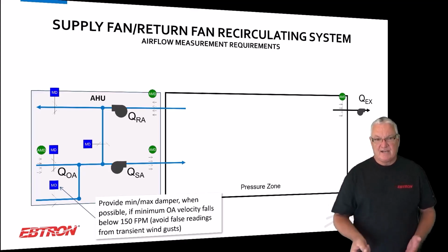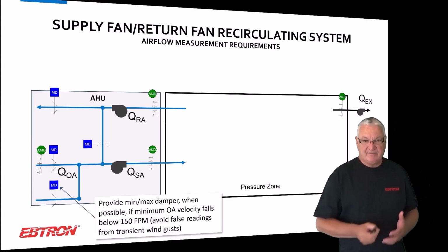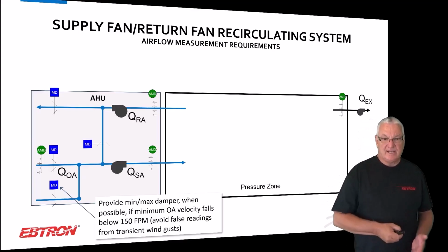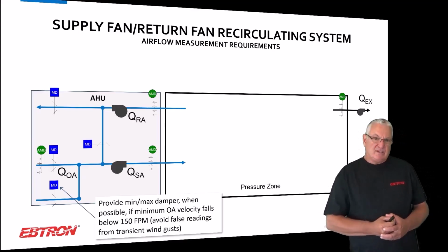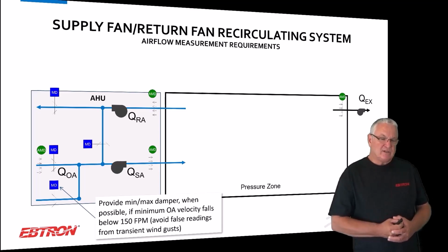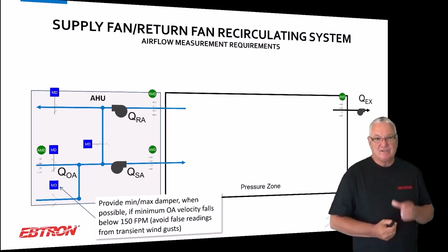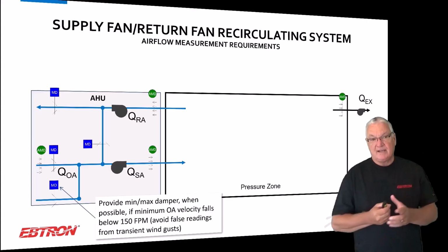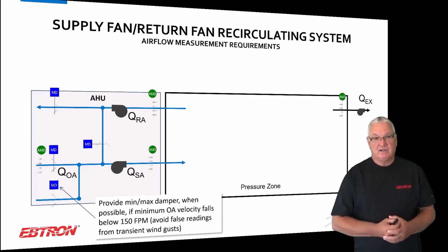There's a reason for that. It has to do with the wind blowing and having the flow meter located close to the outside of the unit. If you're not doing something real custom and it's a package unit, try to select package units where the dampers and where you locate the flow meter are sized smaller than the intake louver or hood, so that these velocities are up.